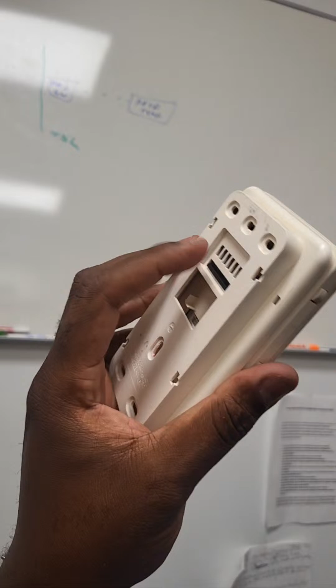With this particular thermostat, this is the older one that I replaced. If I see a communicating error with this Infinity thermostat, here's what an old timer once told me to do to eliminate the inside wire. I can take this thermostat off the wall, sub base and everything, take it downstairs to the circuit board, get a small piece of thermostat wire, and connect it straight to the circuit board at the furnace. I'm basically eliminating my indoor thermostat wires by doing that.